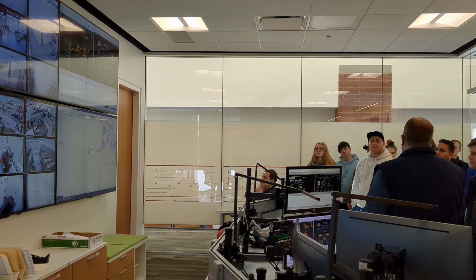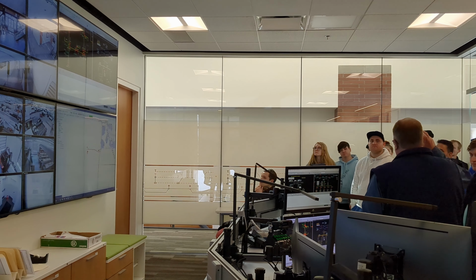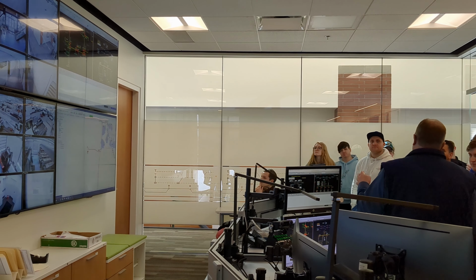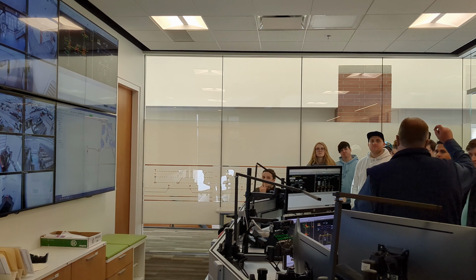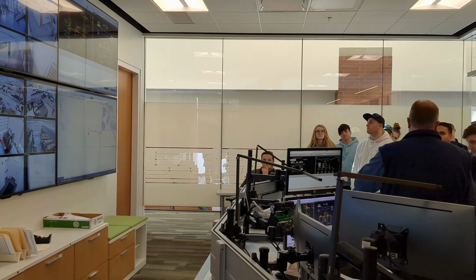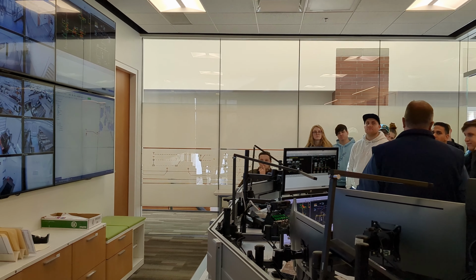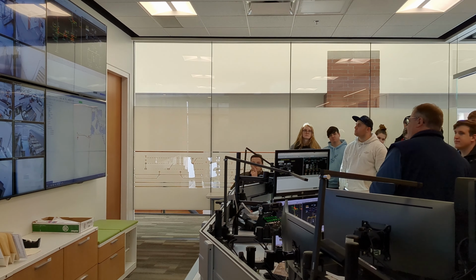So if 3 houses go off, it'll say the transformer is bad. If 40 houses go off, it'll say the line fuse is bad. If the breaker stays open, it'll say 2,000 people are off, right? So there are just different areas of outages.